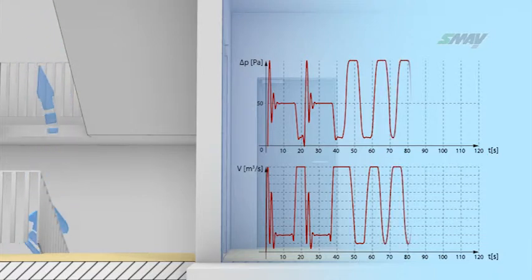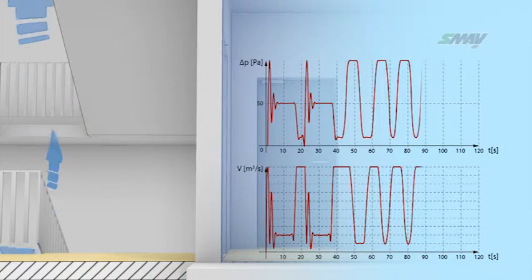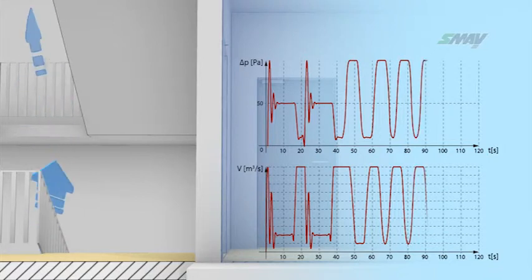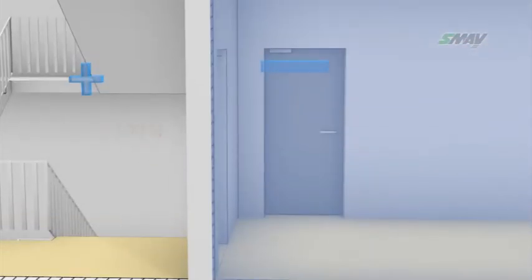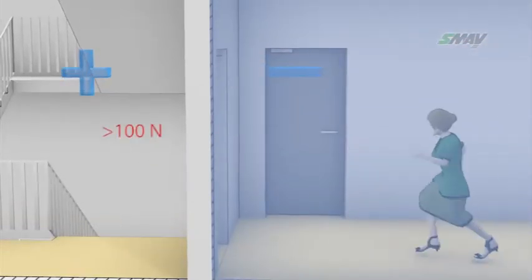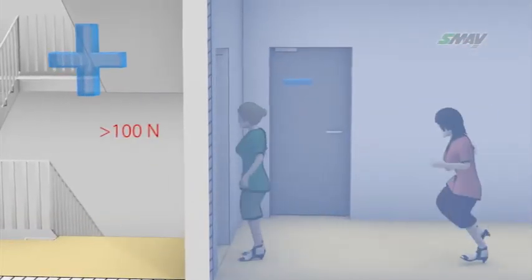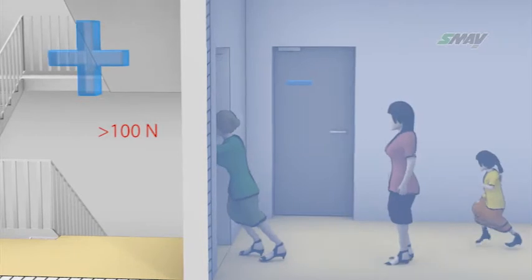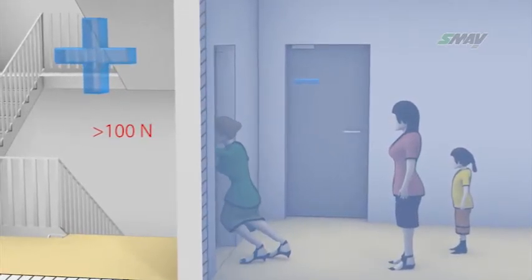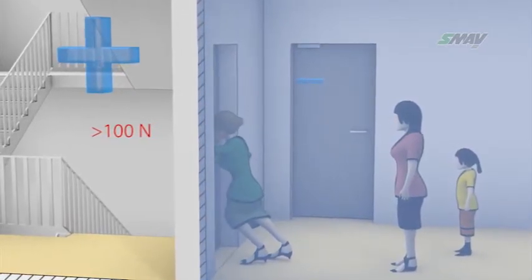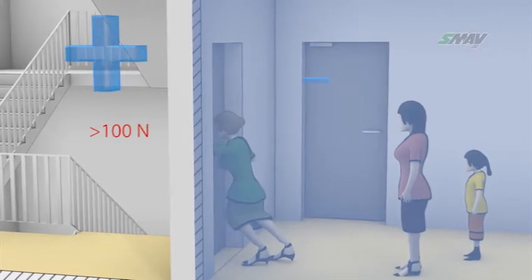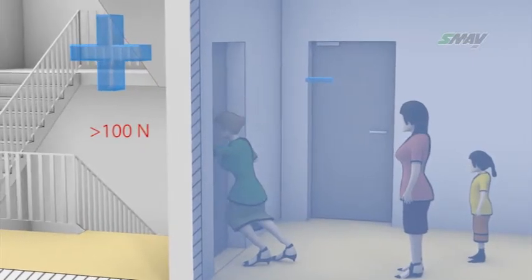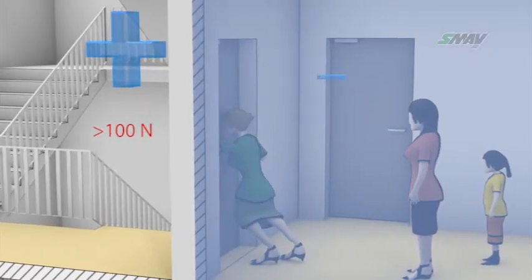For example, the oscillatory increase of pressure to 150 pascals will increase the required door opening force to 200 newtons, which will hinder its opening. The power necessary to open the door rises above the required level of 100 newtons, which may last from 10 to 20 seconds. The staircase will be cut off from the evacuating people.